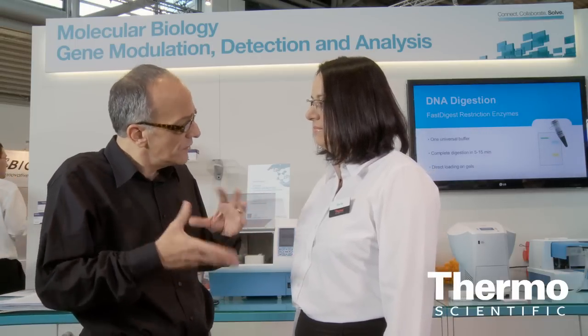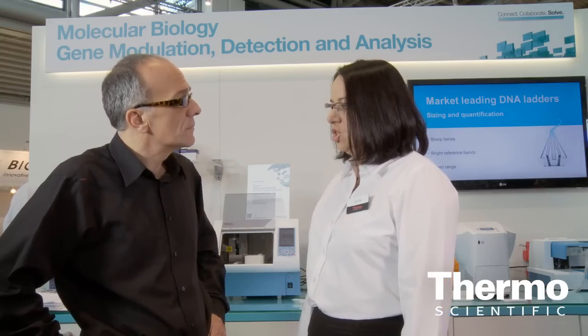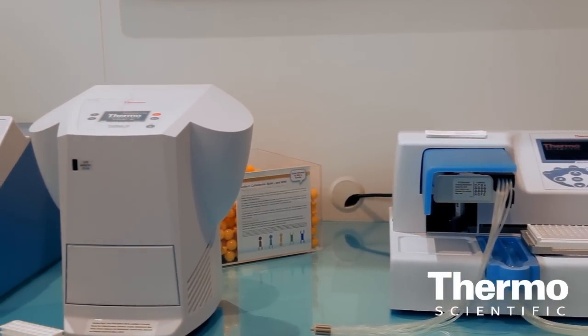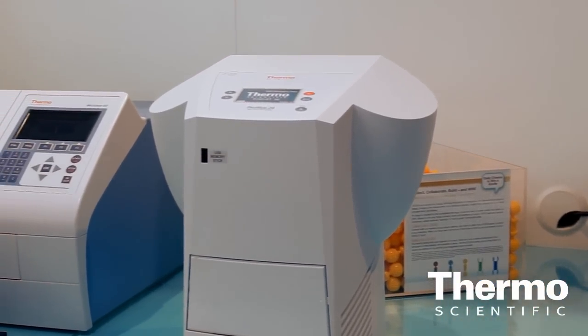And some of the innovative capabilities that we've introduced in this product — it's based on another instrument, the PCR instrument, which is really a very efficient one. The heating and cooling is very, very fast, and also it's very uniform. It's very important in quantitative experiments when you have different samples all over a plate, and you want the heating of each sample to be really uniform. Otherwise, your data will be skewed.